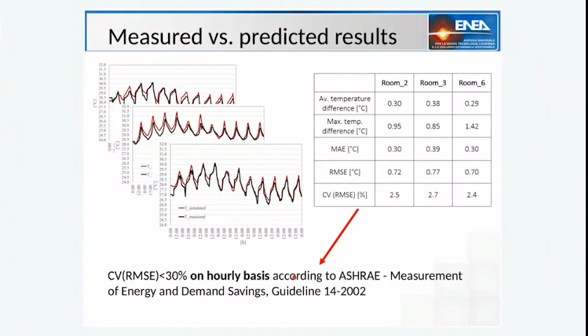And here we have the main performance comparison data: the difference between the simulated and calculated value, as well as the maximum temperature difference. And here some statistical data. In particular, I would like to focus on the last one, that is the coefficient of variation of the root mean square error. The ASHRAE Guideline 14 on measurement of energy and demand savings defines that for hourly data, this indicator has to be lower than 30%. And as you can see here, our value was always below 3%. So we were far lower than the standard, so we could consider the calibration exercise quite satisfactory.